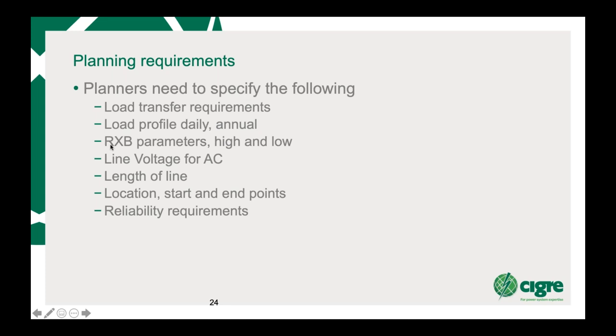Then you need to also know what your R, X and B parameters are, because planners, when they do the load flows, will assume certain R, X and B parameters. You need to understand what those are and if there's a high and a low. So in parallel lines, you might have a request on low R, X and B values because you don't want the power to go all down the one leg and not down the other leg.